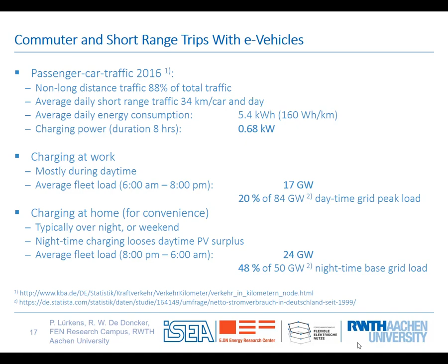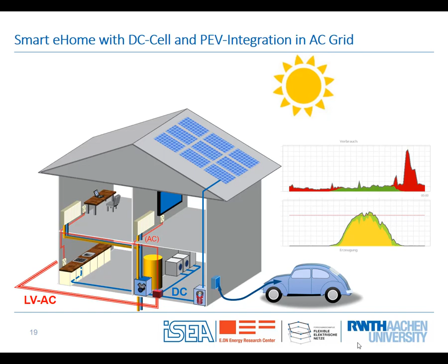This could be the future: a home with an internal DC distribution system for hardwired equipment like a heat pump system and photovoltaics. You could have maybe a 50 kilowatt DC bus peak power for fast charging a vehicle, connected to a low voltage AC 400 volt 4-wire system. That's a possibility to consider, but we see a problem coming with low voltage AC distribution.